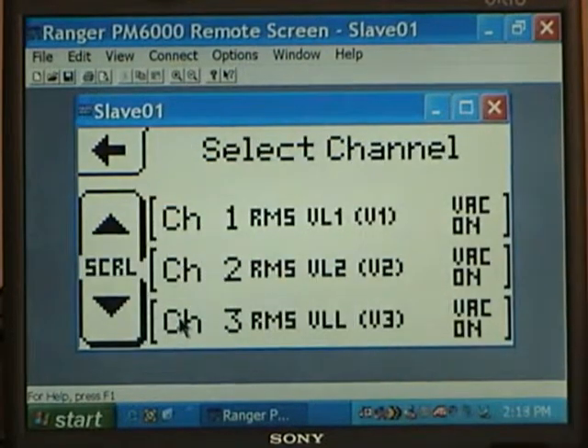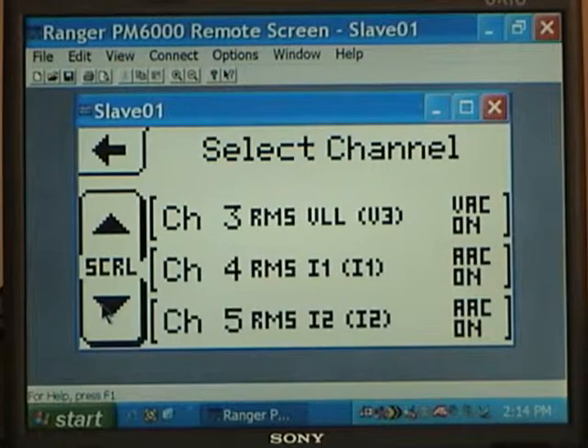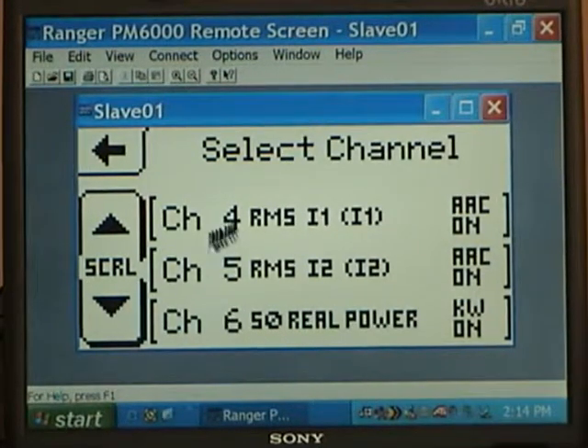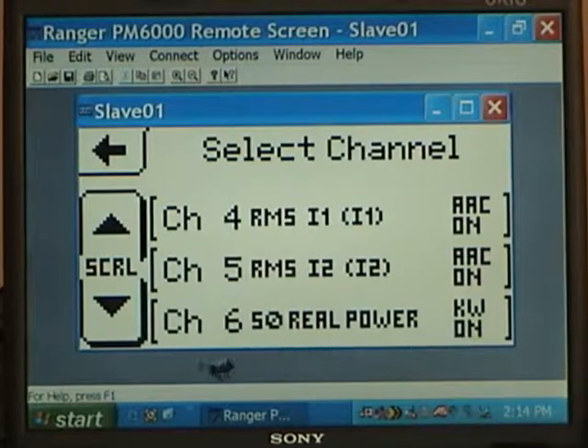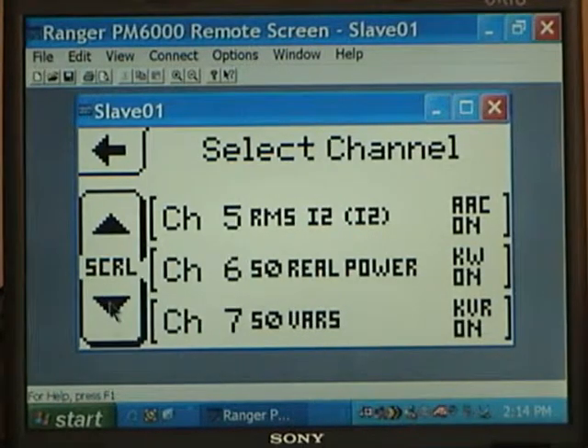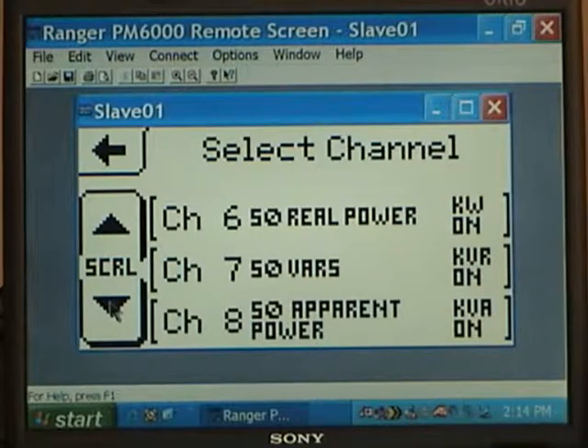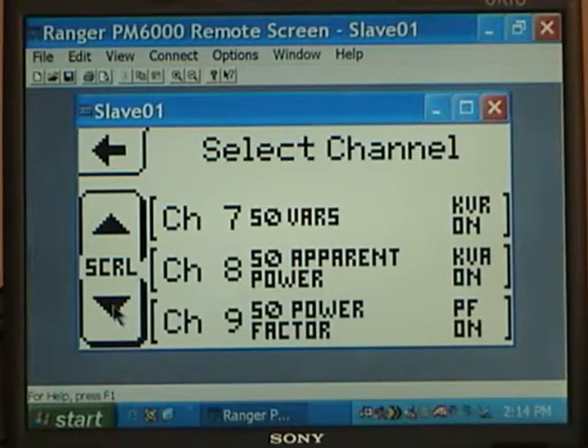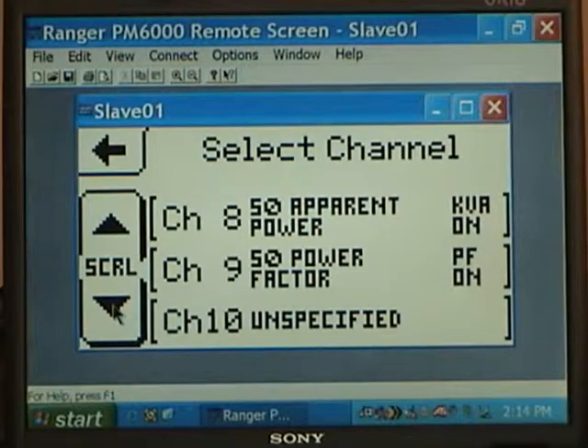Then we have the recording channels here. And you can see in this setup that channels 1, 2, and 3, L1 to neutral, L2 to neutral, and line to line are all volts AC, and they are on. If we scroll down to channels 4, 5, and 6, we see channel 4 is current number 1, L1, channel 5 is current on L2, and channel 6 is KW, real power. Channel 7 is VARs, channel 8 is KVA. Channel 9 is power factor, and then channel 10 is unspecified, and so on.